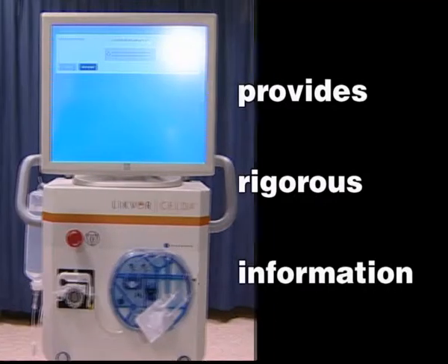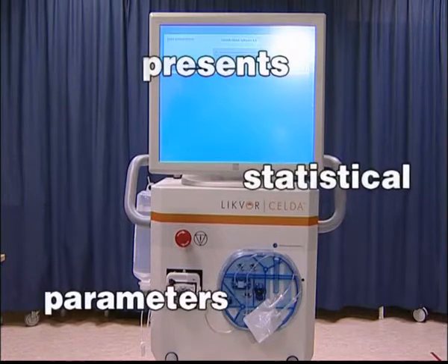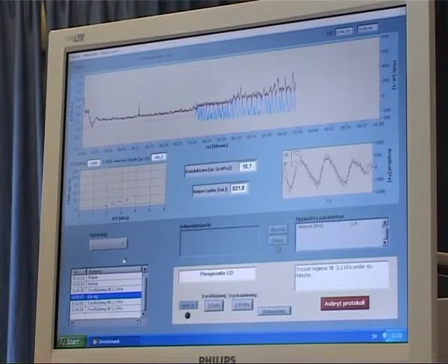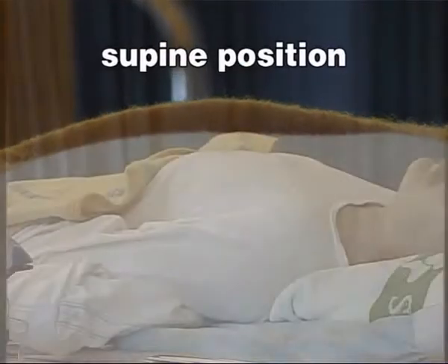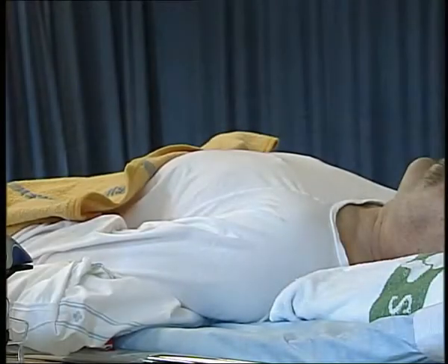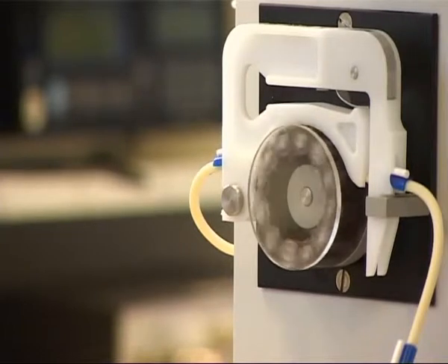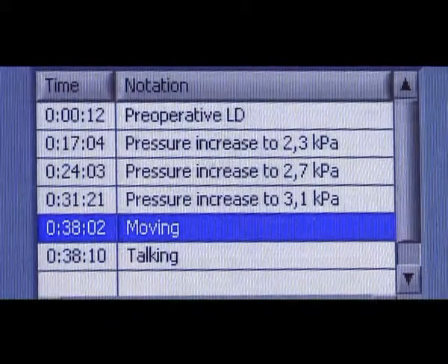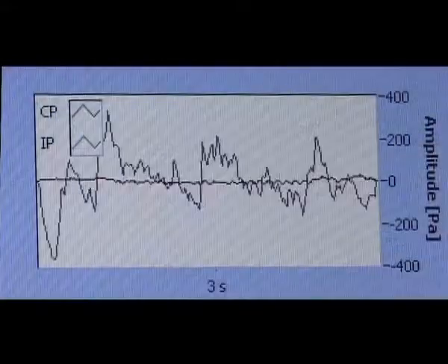The investigation takes approximately one hour, during which the patient is lying in the supine position in a relaxed way, not uncommonly sleeping through parts of the investigation. In addition to the recommended constant pressure method, there are six automated and five manual protocols, including constant infusion and bolus algorithms, to allow for a diversity of investigations.